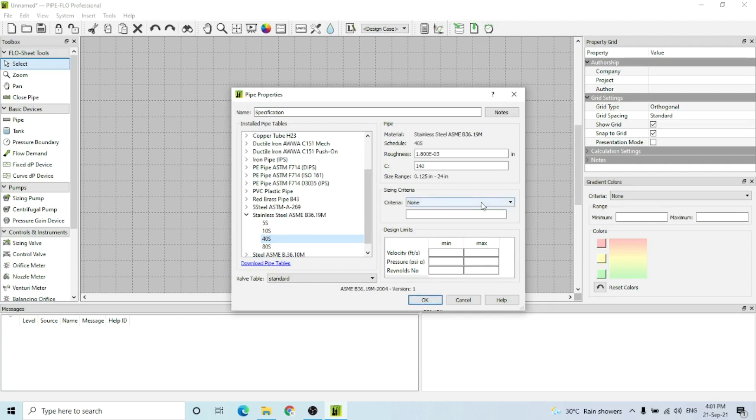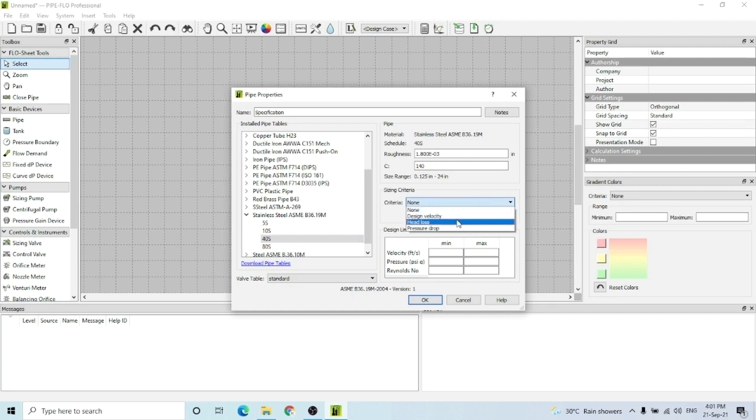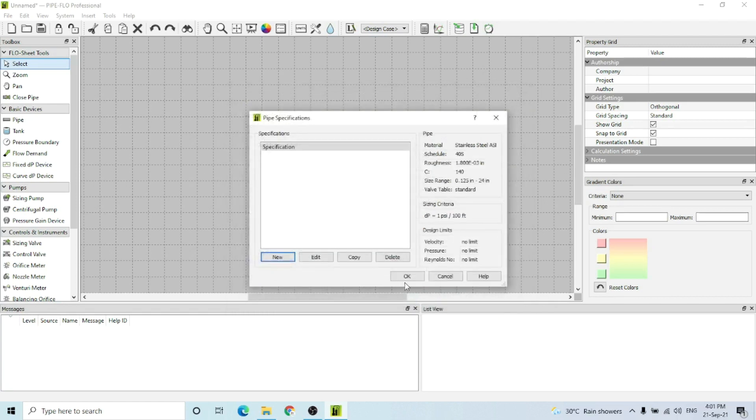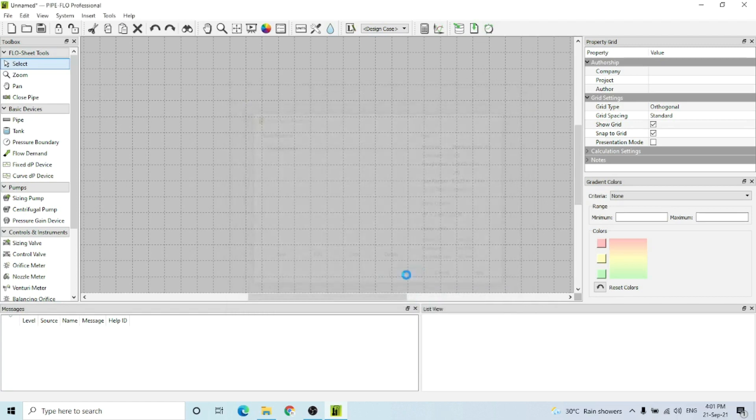The sizing criteria is not necessary, but you can include it. For sizing criteria, I use pressure drop - that is the limit for sizing a pipe. I'm going to use one psi per hundred feet. Now I'm going to select from the Control and Instrumentation tab.